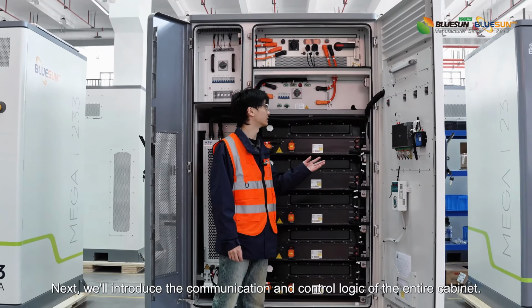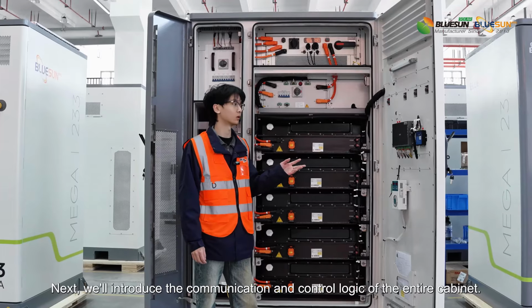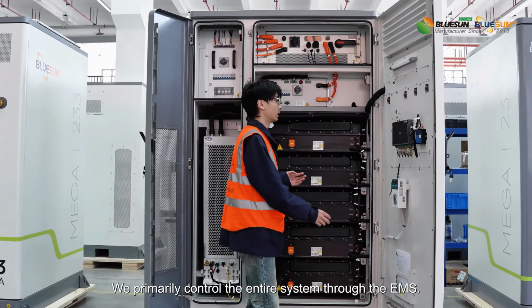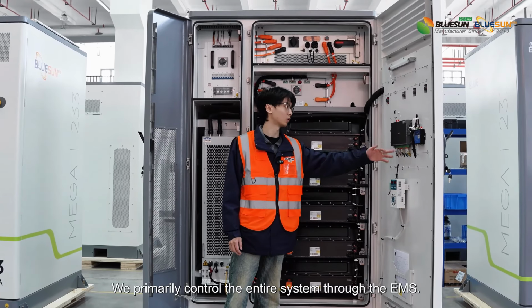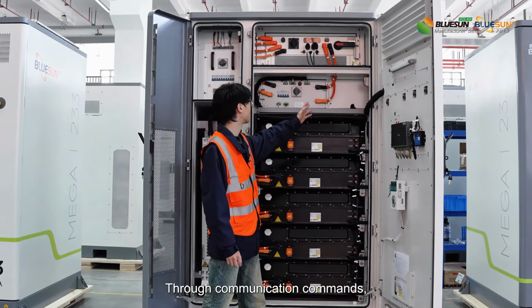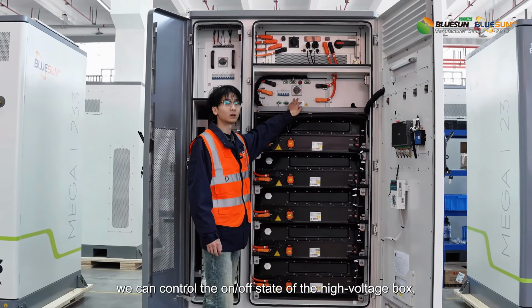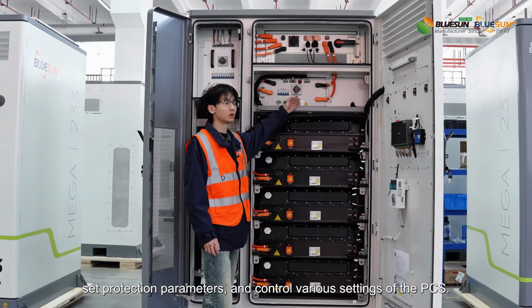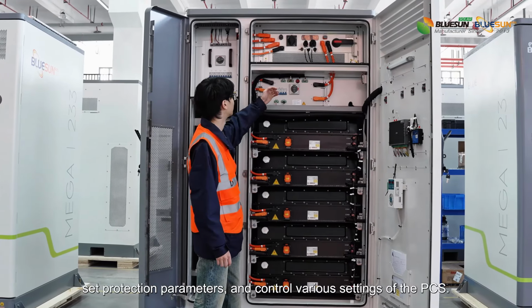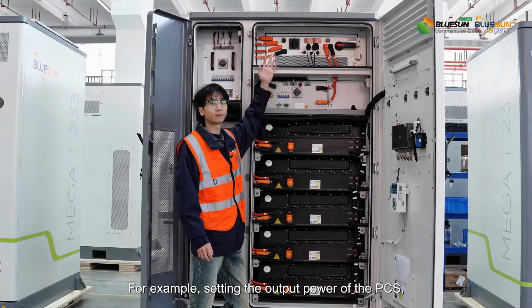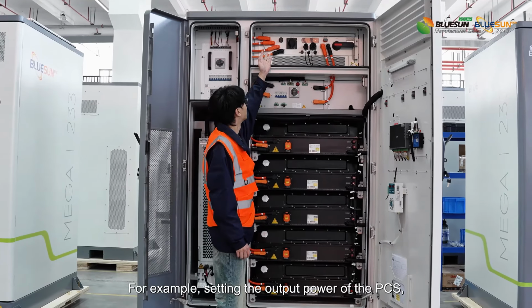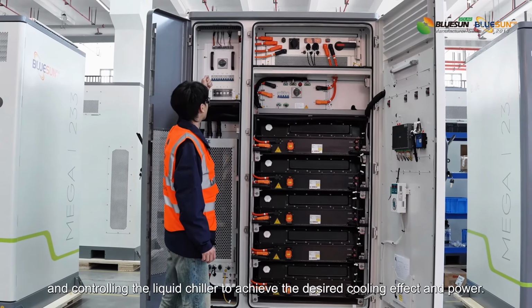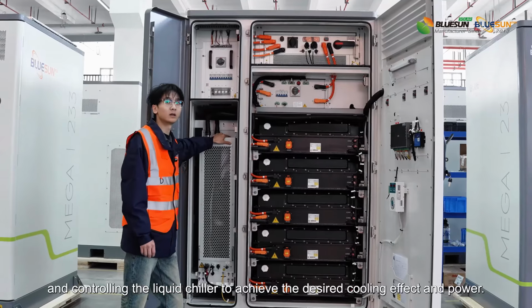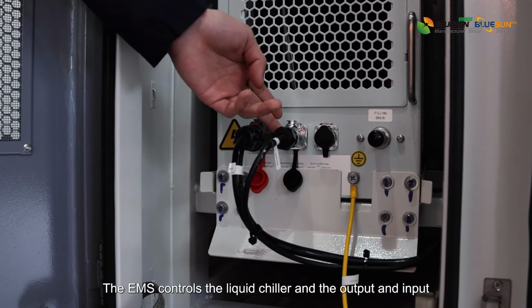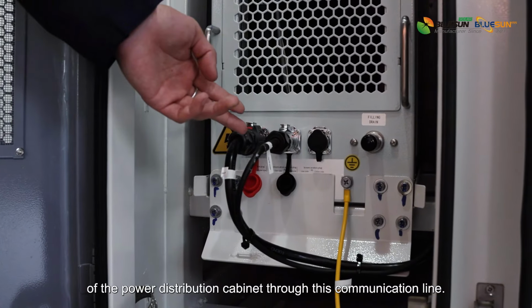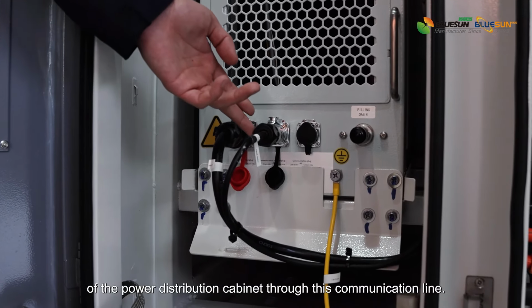Next, we'll introduce the communication and control logic of the entire cabinet. We primarily control the entire system through the EMS. Through communication commands, we can control the on/off state of the high-voltage box, set protection parameters, and control various settings of the PCS. For example, setting the output power of the PCS, and controlling the liquid chiller to achieve the desired cooling effect and power. The EMS controls the liquid chiller and the output and input of the power distribution cabinet through this communication line.